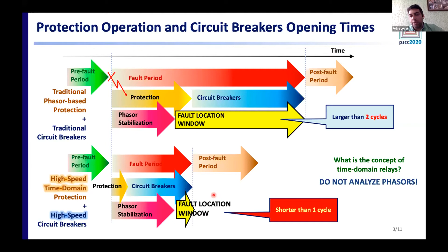But when we are talking about fault location, the fault distance estimations must be taken only after such a phasor stabilization time. So on average, we typically have a fault location window larger than two power cycles. But what is the concept of time domain relays? It is simple. They just do not analyze phasors. And so if we use high-speed time domain protection associated with high-speed circuit breakers, we know that circuit breakers are evolving to be faster than those used in today's technology. The fault period will be reduced as well. The phasor stabilization time is removed from the protection tripping time, but it cannot be removed from the phasor-based fault location process, in such a way that fault location windows shorter than 1 power cycle are expected.